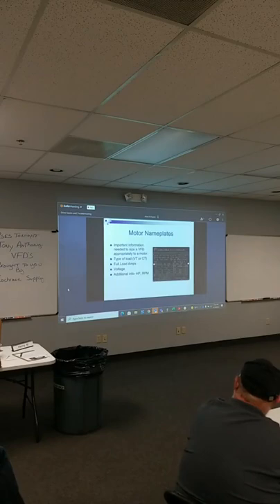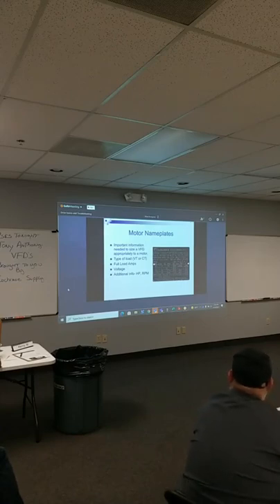All right, any questions on variable torque, overspeeding the drive, fans, or anything like that? Once again, make sure you check the fan curves. I want to go over the motor nameplate here. This nameplate, I've got to get another picture, it has way too much information on it. If you get a call and the customer says, I've got a 10 horsepower motor on a fan and I would like to put a drive on, somebody tell me the questions you would ask. What do you need to know?